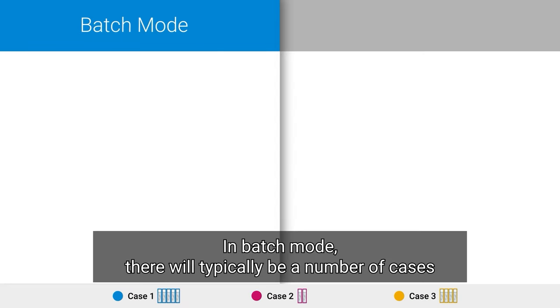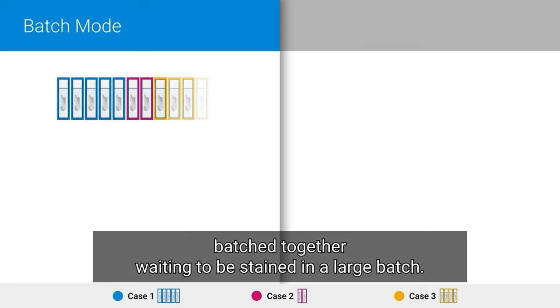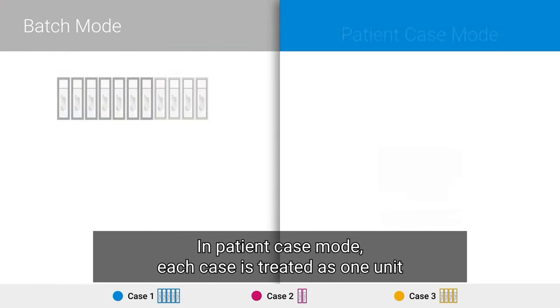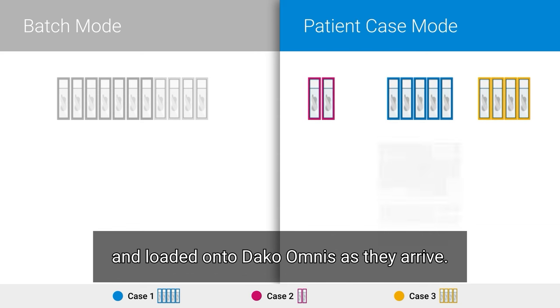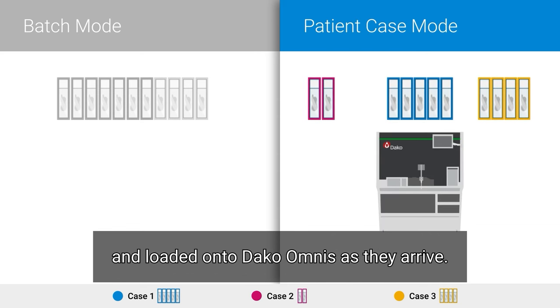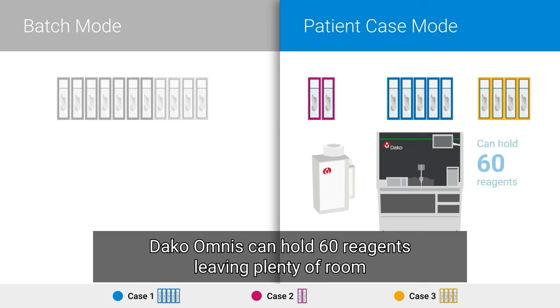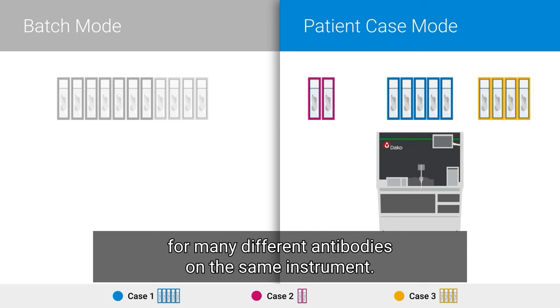In batch mode, there will typically be a number of cases batched together waiting to be stained in a large batch. In patient case mode, each case is treated as one unit and loaded onto Dako Omnis as they arrive. Dako Omnis can hold 60 reagents, leaving plenty of room for many different antibodies on the same instrument.